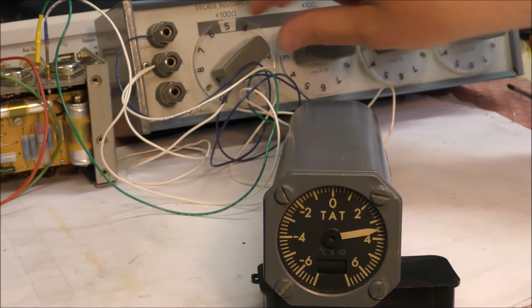We can see that we have the correct temperature. I can change 1 ohm more and less, so we can see it's exactly 362 ohms. The adjustment of the 0 is perfect, but it seems there is a problem with the adjustment of the gain of the amplifier or the servo control loop.